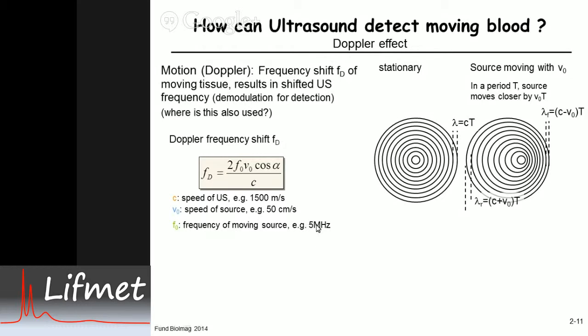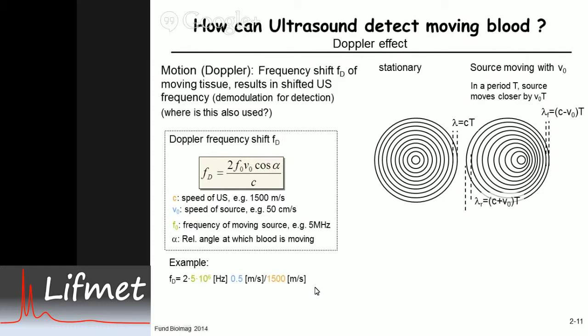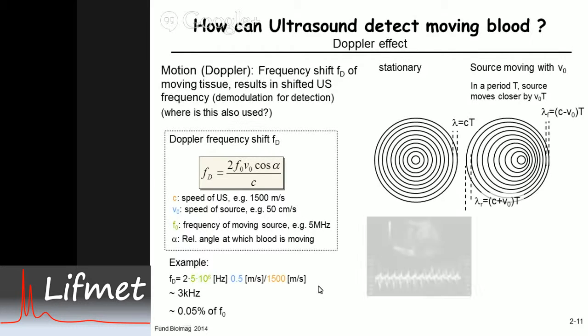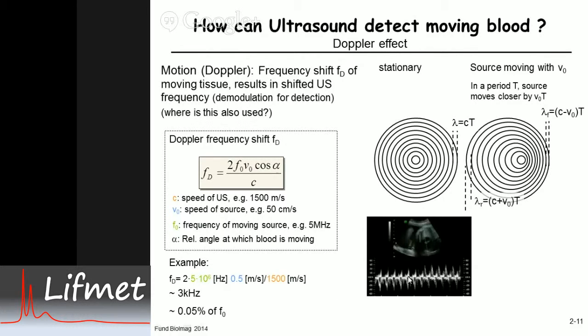For this example, the ultrasound frequency is 5 megahertz. Plugging in the factor of 2, the velocity of half a meter per second, and the wave propagation velocity, you get a Doppler frequency shift of 3 kilohertz. That's only 0.05% of the ultrasound frequency — a small shift — but the good news is that with today's electronics and demodulation, a 3 kilohertz shift is easily measurable.